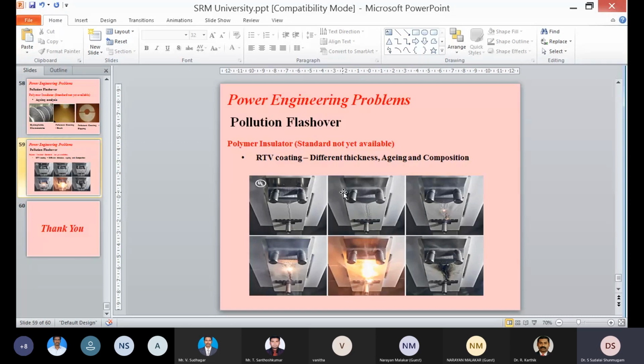But nowadays, another research happening in that area is, instead of operating a circuit breaker below 220 kV, significant research is happening on how we can use a surge arrester which is able to provide enough isolation in systems below 220 kV. Earlier, when it came to surge arrester design and development, we were predominantly using them only for lightning impulse voltage. Now that is not the case. This polymeric insulation has found its depth even in surge arrester design. Nowadays, even post insulators and support structures are coming out of polymeric insulator only. And because of that phenomenon, we are also into research, especially after ZnO blocks came into the picture. There has been significant research on how to use surge arresters for power frequency overvoltage faults.